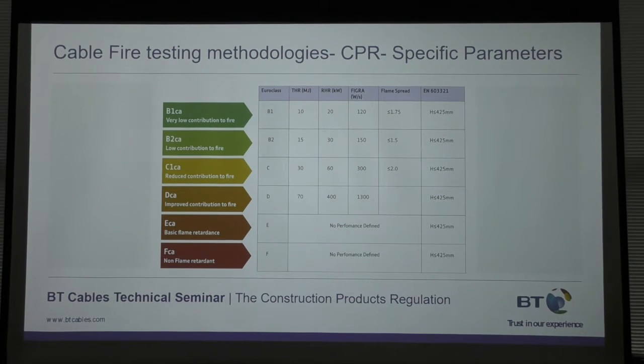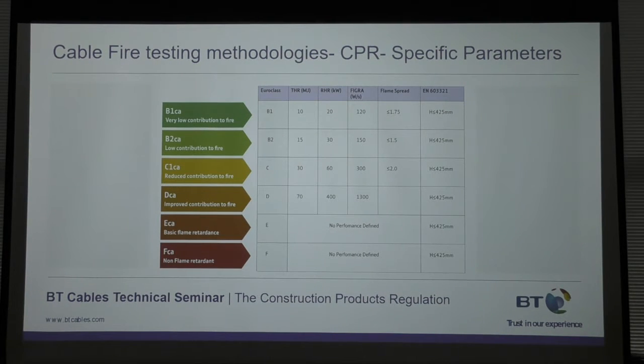It's just pure hydrocarbon with no flame retardancy at all. Then ECA, where it says no performance defined, just H has to be less than or equal to 425. That end column is EN 60332 part 1, which is the Bunsen burner test. So ECA is the very baseline level, which has to pass the Bunsen burner test.